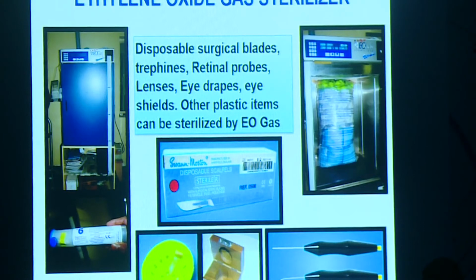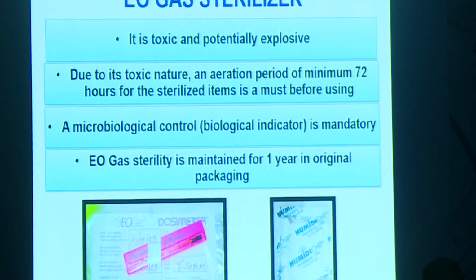Ethylene oxide gas sterilizer, as I said, for heat sensitive instruments this can be used. Disposable surgical blades, trephines, retinal probes, lenses, drapes, etc. can be sterilized by ethylene oxide. But we should be careful that it's a toxic and potentially explosive thing. So due to its toxic nature, an aeration period of minimum 72 hours for the sterilized items is a must before using the instruments. A microbiological control or a biological indicator is mandatory, and the sterility is usually maintained for a year if it is in the original packing.